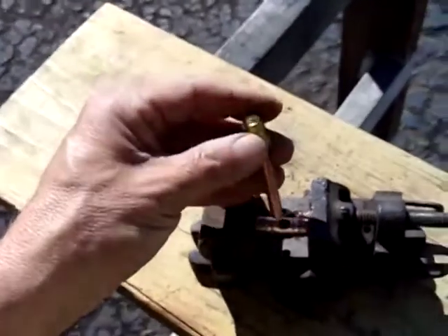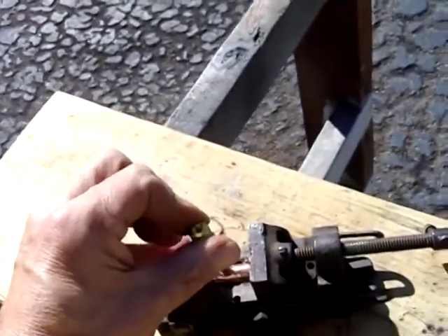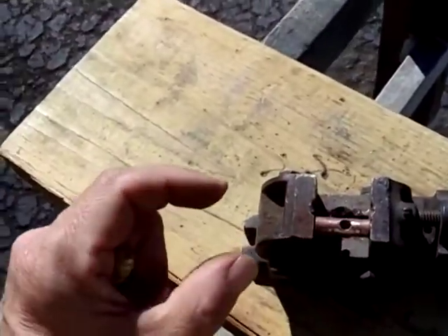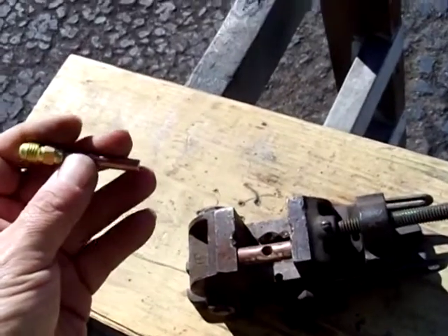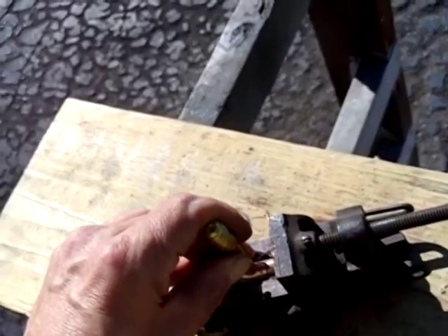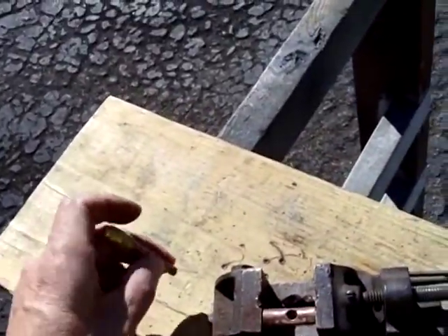I'm away from the dehumidifier. I'm trying to braze this. I cut this little piece of tubing. I swaged it out just slightly to fit over that tube. A full swage would have been too much of a gap. And now I have this thing. I'm filing it from both sides to fit kind of nice. I think that's good. And I'm going to try to braze that together to make the T. And then I'll slide that on there and braze it onto that.